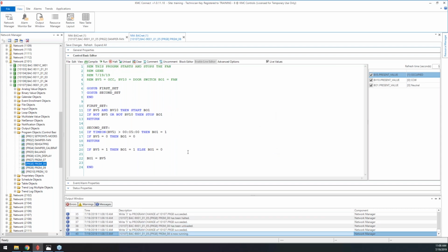Without putting that third GOSUB in, this program would actually never get to lines 20 or 22. It would run 10 through 13 and then 15 through 18, and then the program would end back here, never hitting that 20. So if we wanted to run something on lines 20 or 22, we'd want to put a condition in to jump down to those lines.